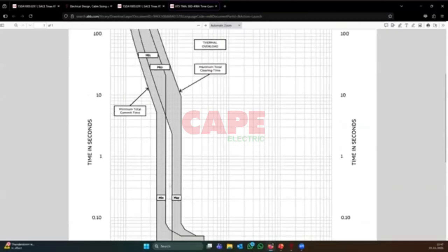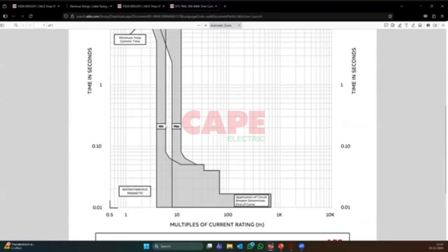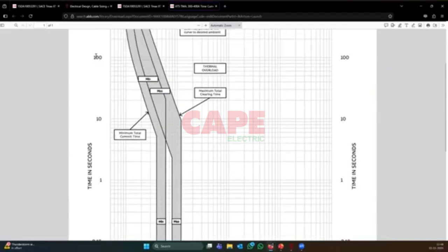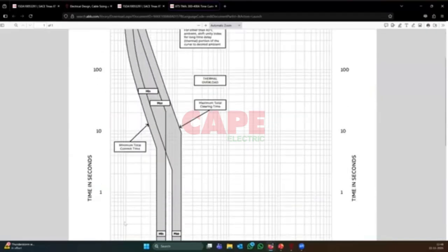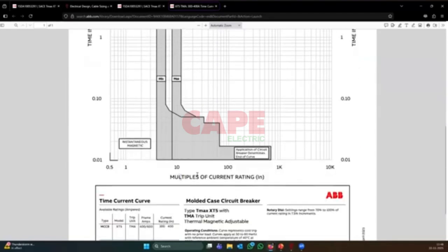So now I am going to take the maximum setting. I hope everybody can see my cursor. At the maximum, this x-axis, the 0.5, 1, 10, 100, 1K and 10K, is the multiples of current. And the vertical axis is the time in seconds: 0.01 seconds, 0.1 second, 1 second, 10 seconds, 100 seconds, 1000 seconds. This is the time in seconds, and this is the multiples of current.